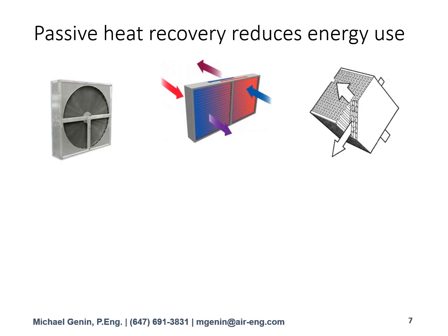So what has become popular in terms of energy savings when we talk about make-up air units is passive heat recovery. And these things might exist in the form of a heat wheel, which is basically a rotor that brings heat from one airstream to another. There are also heat pipes, which are tubes with a small amount of refrigerant, and they move heat from one airstream to another by depending on the change of state in the refrigerant. And then there are also, another common one, fixed plate or energy cores.